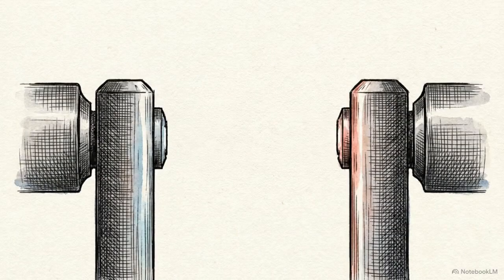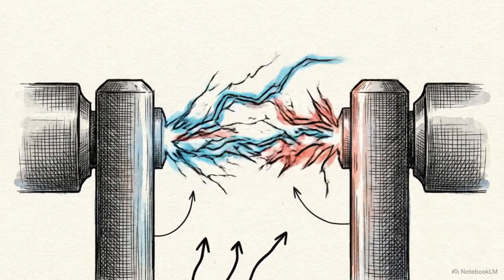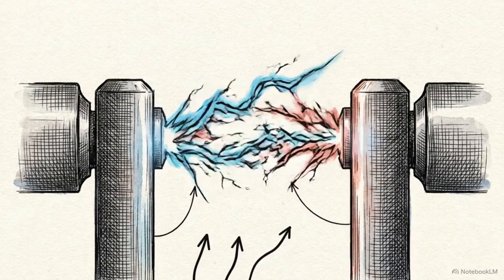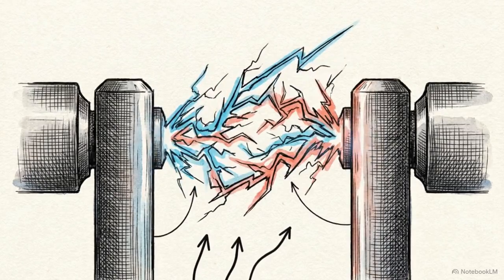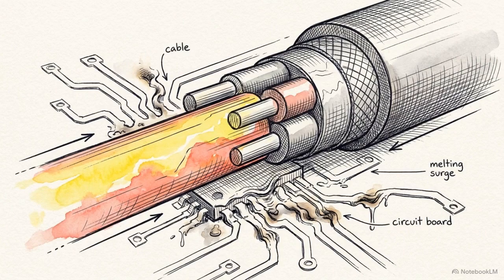In extreme environments, such as a medical defibrillator or industrial motor drive, common mode noise can spike to 2,000 volts. At kilovolt levels, a continuous electrical wire will transmit that massive surge directly into the processing equipment, causing catastrophic failure.